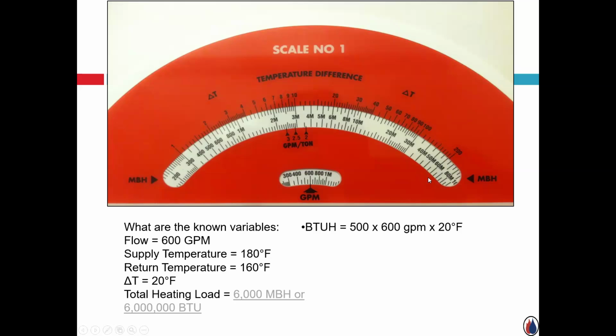And then I said I had a leaving temp of 180, a return temp of 160, so 20-degree delta T. So all I want to do is find 20 up here in that delta T temperature difference scale. Read straight down, 6,000 MBH or 6 million BTUs. So I'm in that boiler room. I see those conditions. That's what's happening right now. The plant is experiencing about 6 million BTU load.